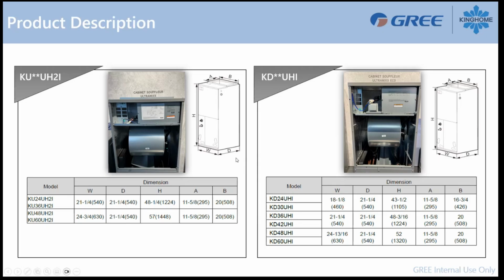There's a tip I want to focus on a little bit, which is the dimension of the supply outlet. The A and B dimensions are about 12 by 20. This is really important when you fix your ductwork, to match this dimension and make sure you have enough space to open the top lid on the air handler. That will greatly help you during the installation of the duct heater. Whenever you are installing this kind of air handler, I strongly suggest using this dimension for your first joint, your first ductwork cabinet on the supply, to make sure you fit it.